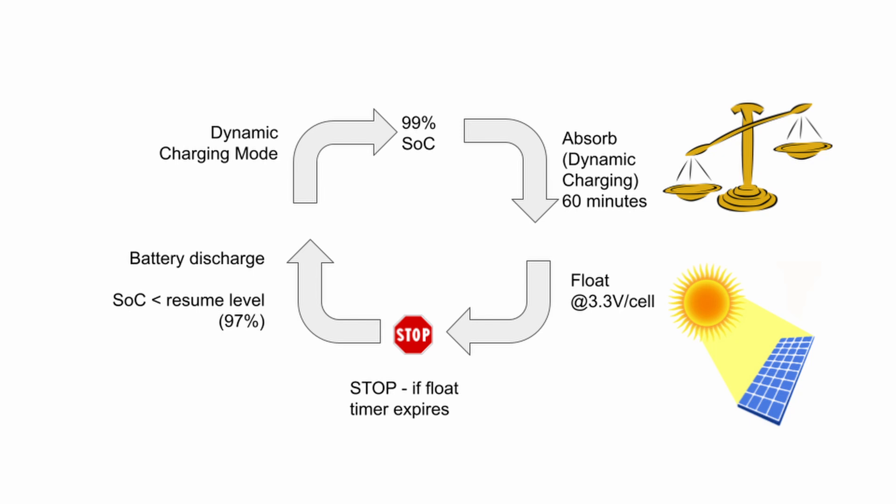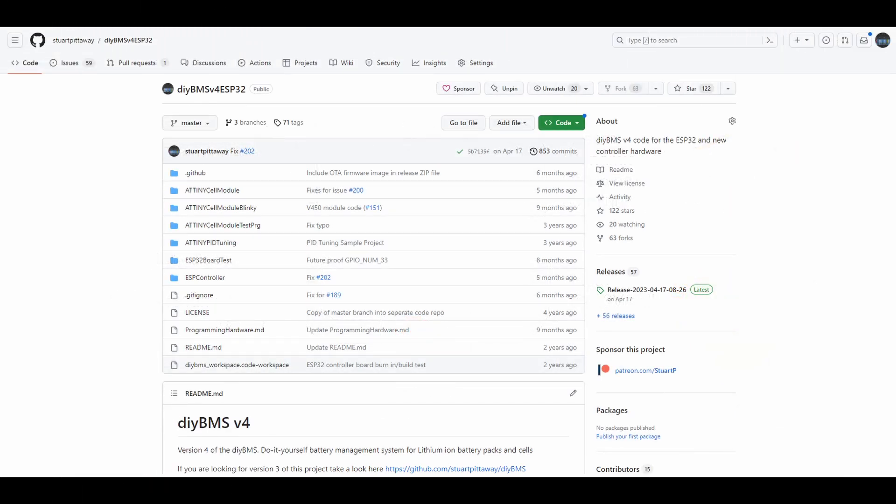So in a typical charging cycle, the battery will be charged at 99%. It will then creep up to 100% and balance during the absorbed mode. Float mode uses the battery nominal voltage, so you won't charge the cells any further. And as energy is taken out of the battery, it will drop below the resumed state of charge level before being recharged back to 100%.